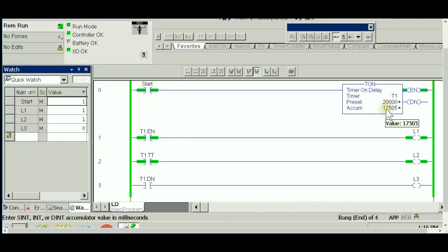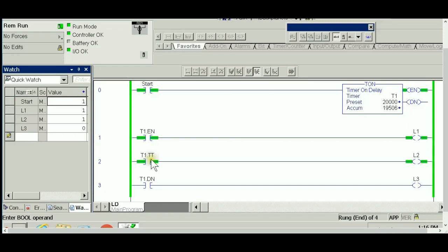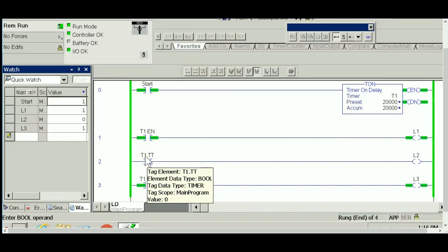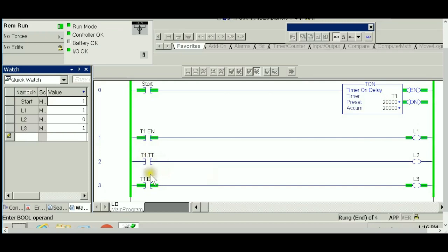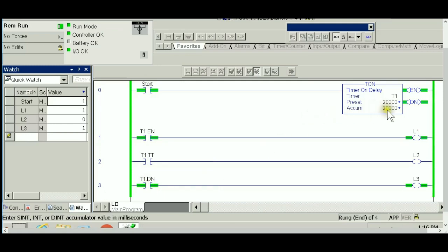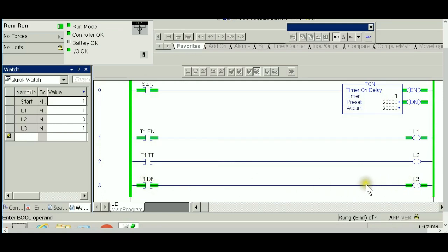Timer timing means the timing operation is in process—the timer is enabled and the accumulator is still less than the preset value. As long as accumulator is less than preset, timer timing is on. Once the accumulator hits the preset value, timer timing is zero because it's done timing. The flag telling us the accumulator reached the preset is the done bit, driving light three.